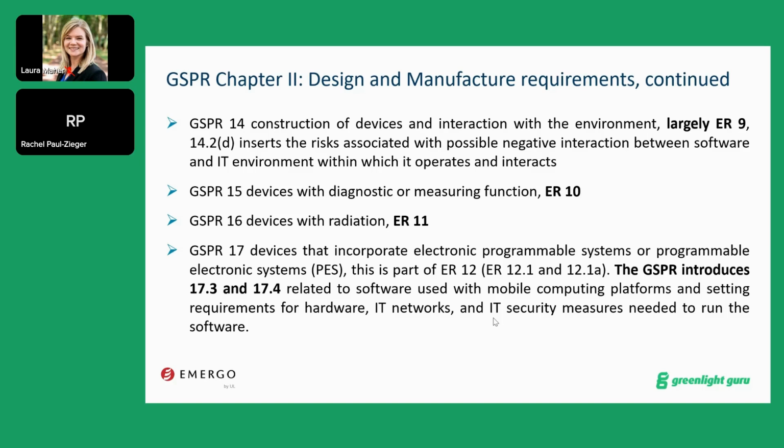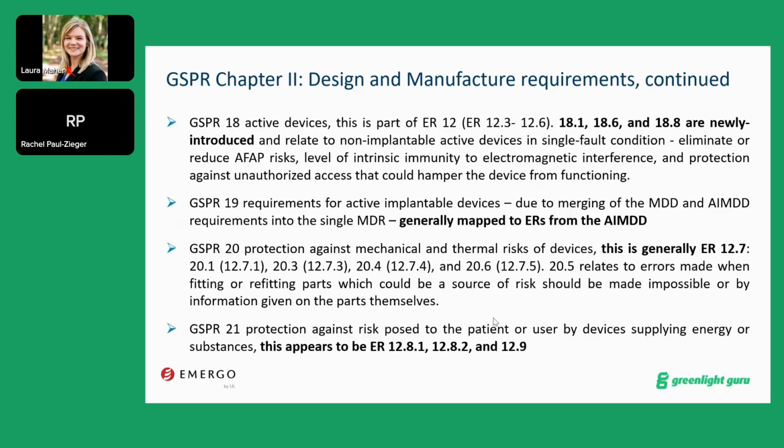Now you have more extended requirements in GSPR 17 related to software used with mobile computing platforms. GSPR 18, you have newly introduced requirements related to non-implantable active device. GSPR 19, you have in fact the requirements that come from the active implantable medical device directive.